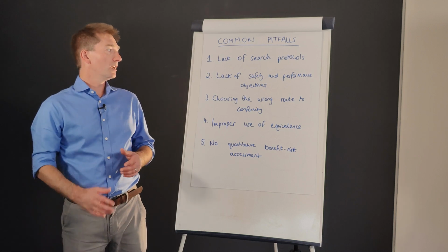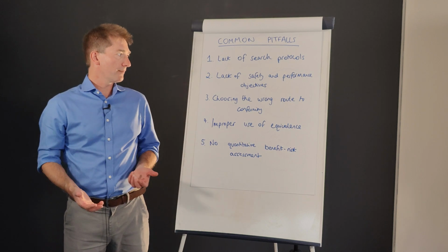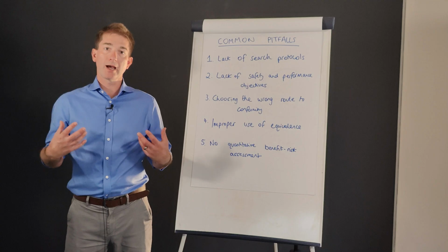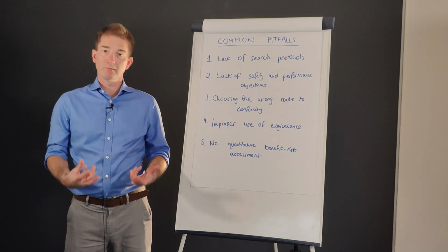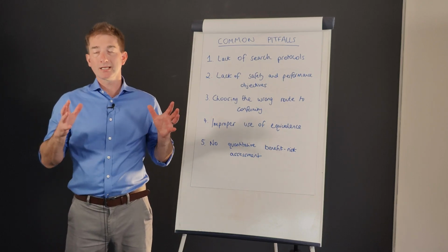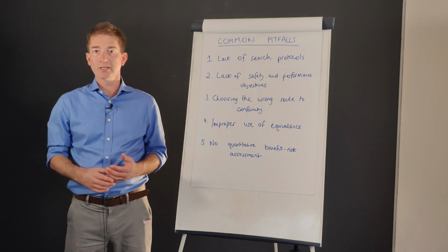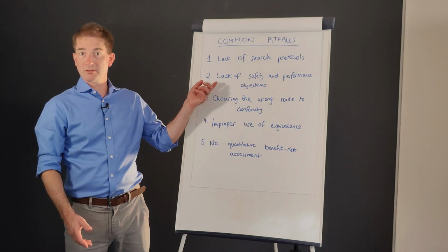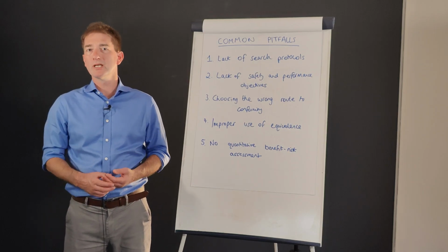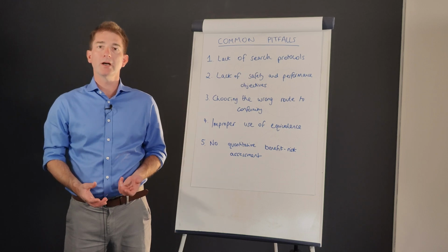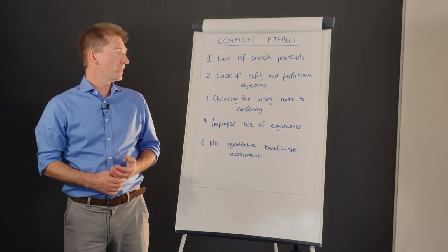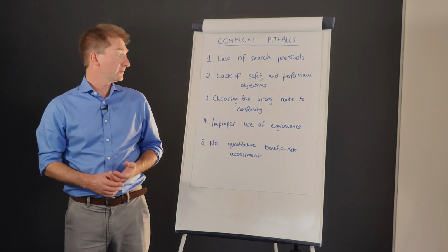The next one that we see really time and time again is lack of safety and performance objectives. If you cast your mind back to the first video in this series, we talked about how these set out benchmark levels of safety and performance derived from devices that are similar to yours. And your device must be at least non-inferior to these values. But time and again, this just isn't done. So a state-of-the-art review is performed, but nothing meaningful is done with it. It's really important that the data you find from the state-of-the-art is analysed, brought together, pooled and weighted to produce meaningful, quantitative safety and performance objectives.